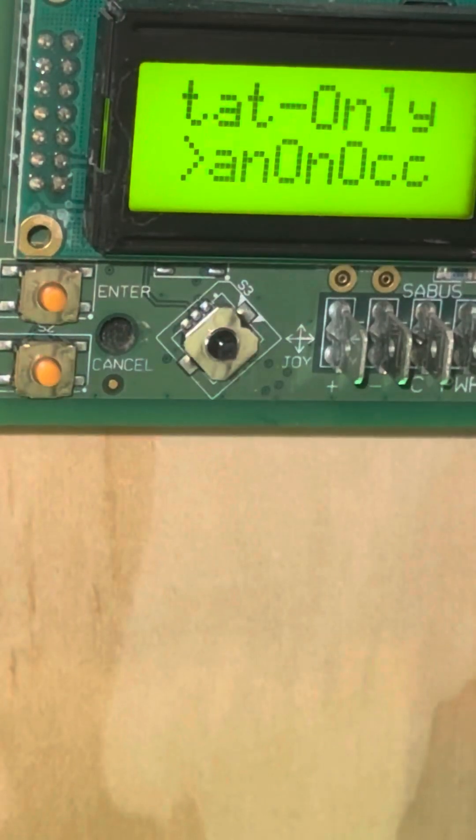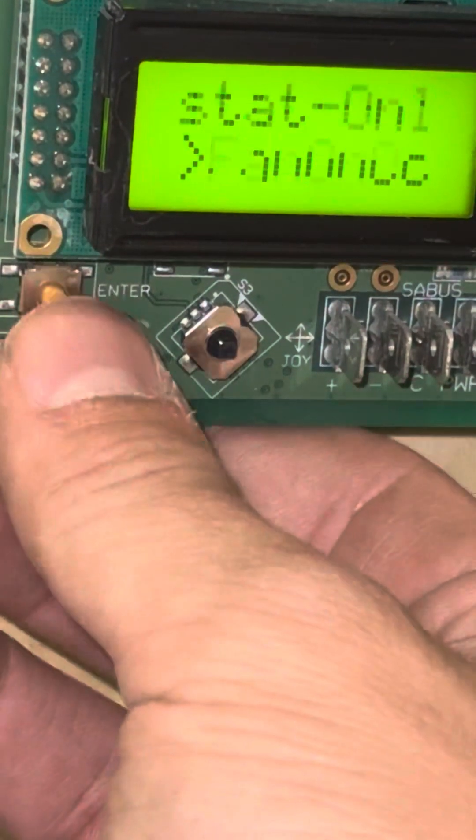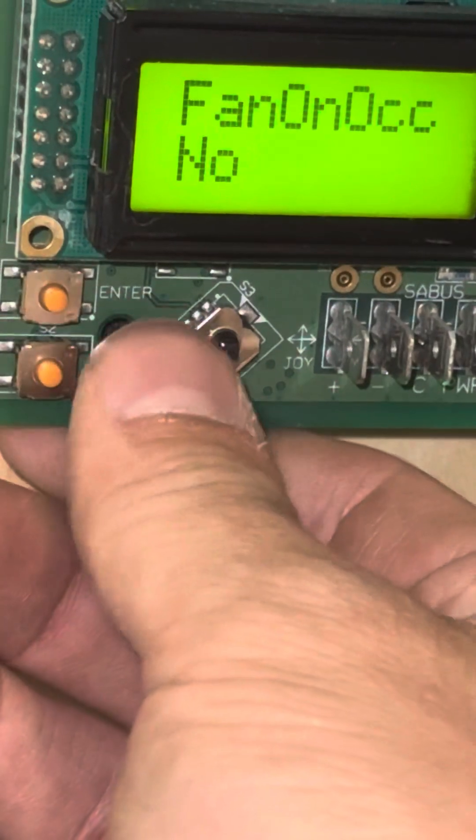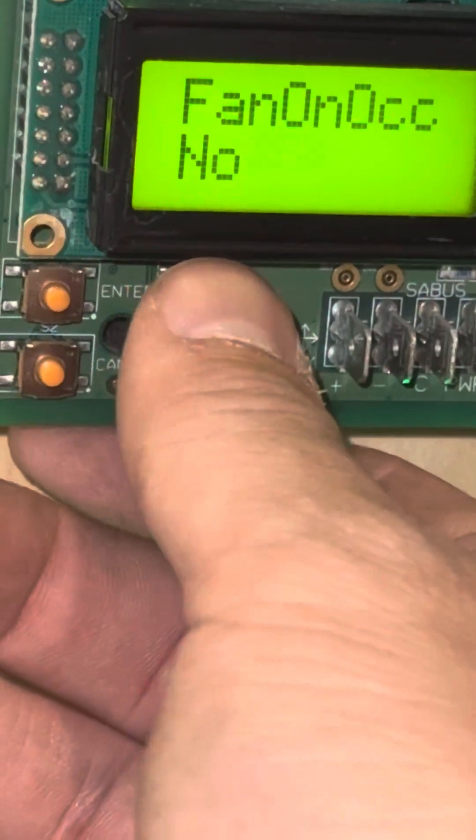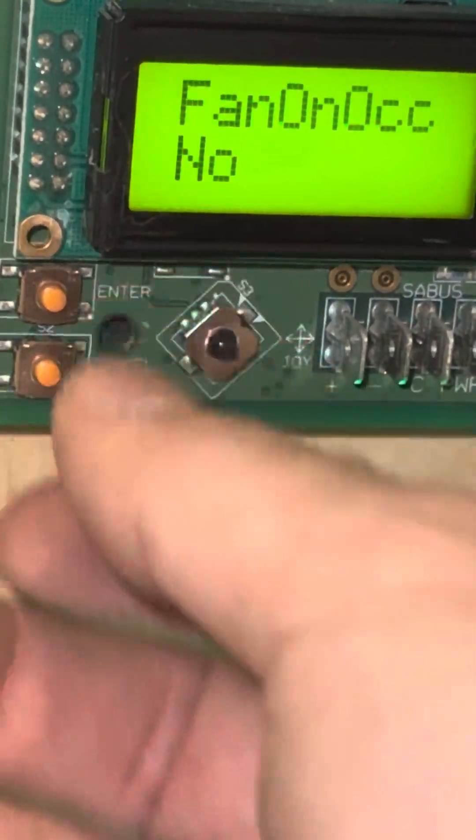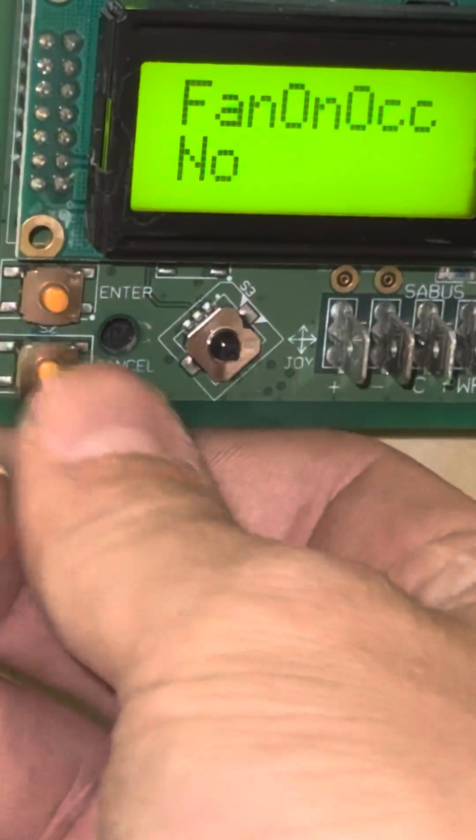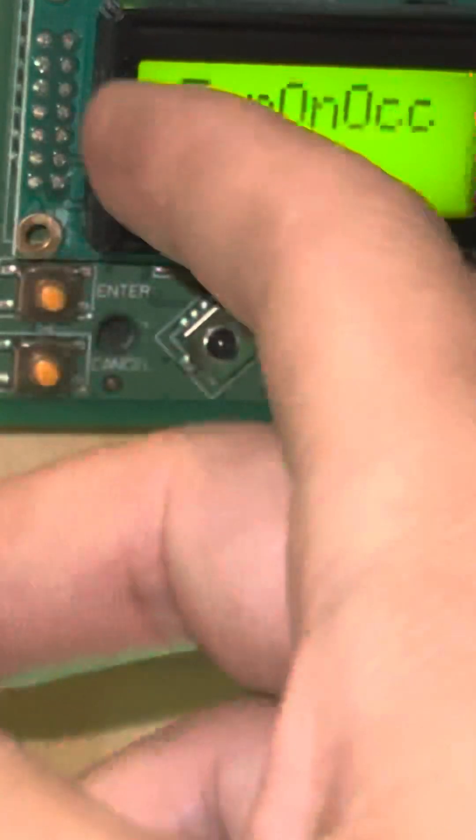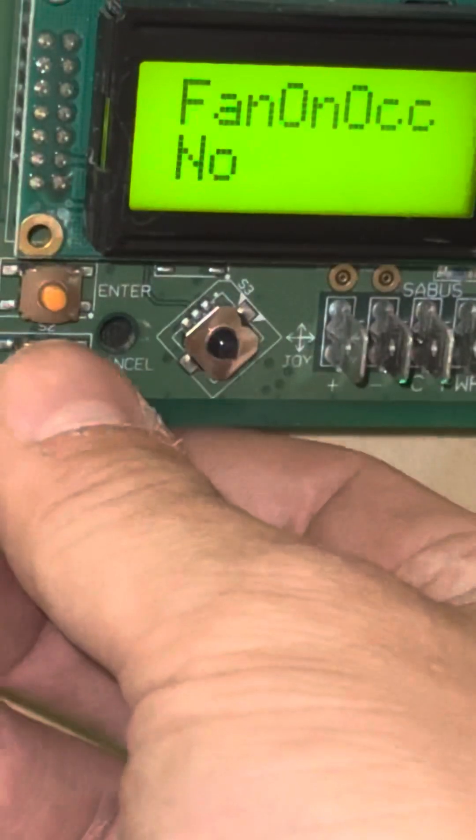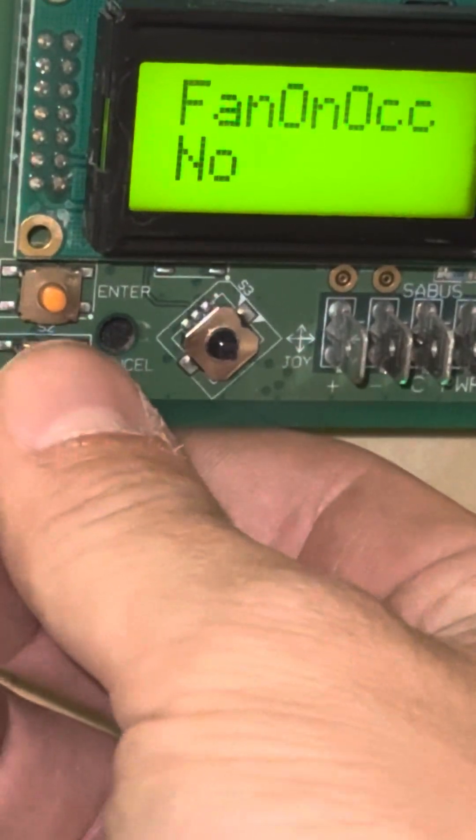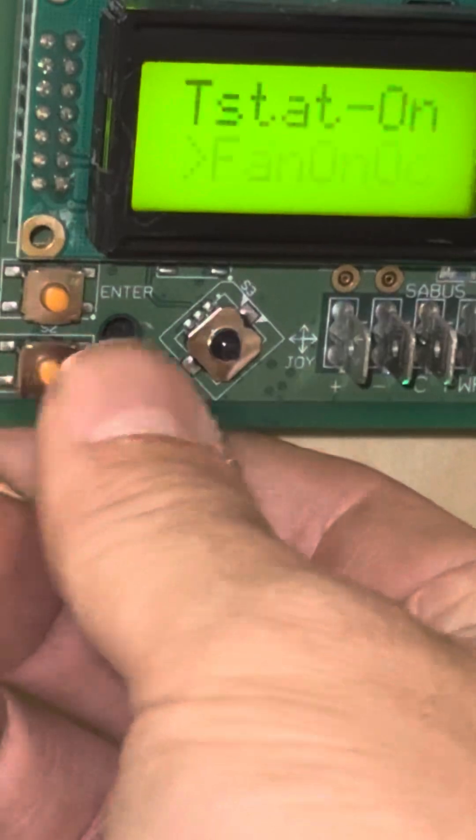Fan on OCC: do I want my fan to be on whenever I'm in occupied mode? A lot of people will want to change this option to no. It usually comes from the factory set to yes, so if you have the fan running all the time, you might just have to change this parameter from yes to no.